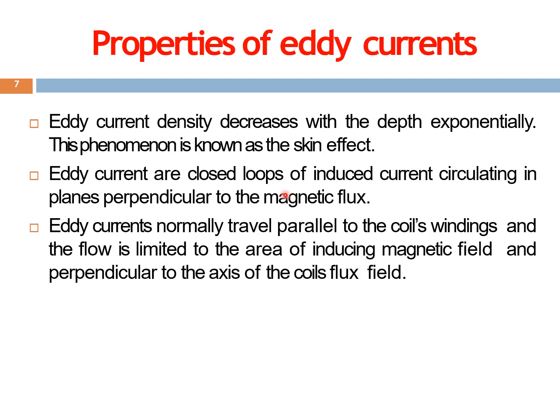Before we move on to the process, we need to know the different properties that are associated with eddy currents. The first one is that the eddy current density is decreasing with the depth. As the depth or the thickness of the material increases, the density of the eddy current is decreasing. How is it decreasing? It is decreasing exponentially. That is, the exponential decay of eddy current density with the depth or increase in thickness is known as the skin effect.